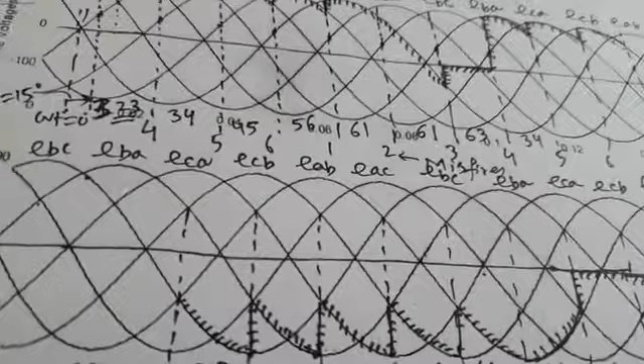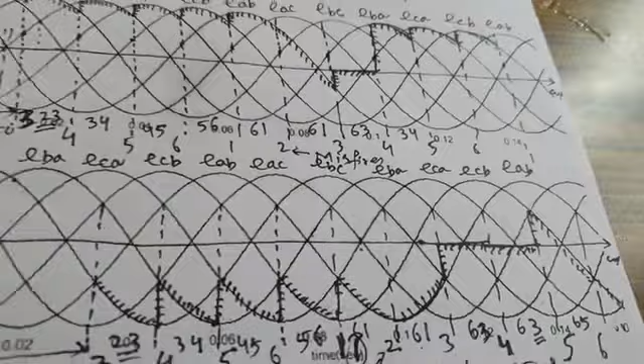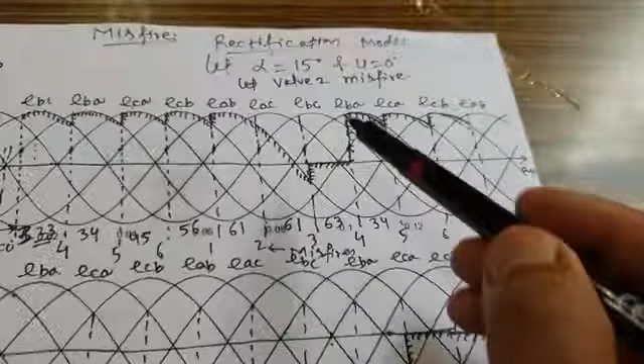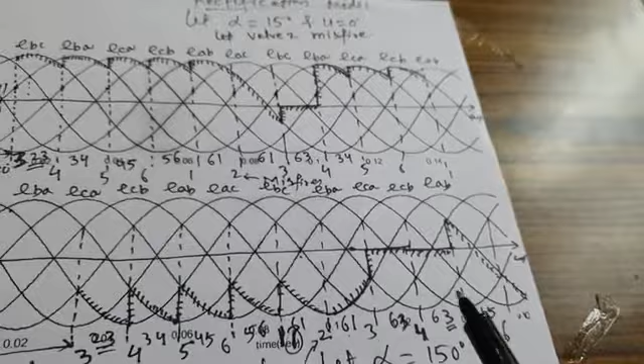So we can say that the load voltage pattern with the misfire is changed. Now if you compare the load voltage waveforms for misfire, both in rectification mode as well as inversion mode, we find that this misfire is more severe in inversion mode than in rectification mode. Because in rectification mode, the load voltage becomes 0 for a 60-degree interval. But for inversion mode, the load voltage becomes 0 for 60 plus 120 degrees. So that is why misfire is more severe in inversion mode of operation than in rectification mode of operation.